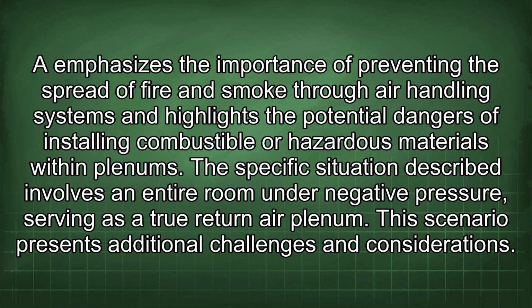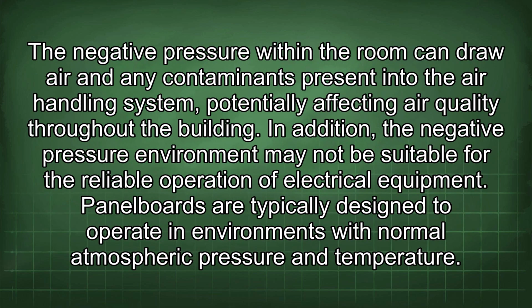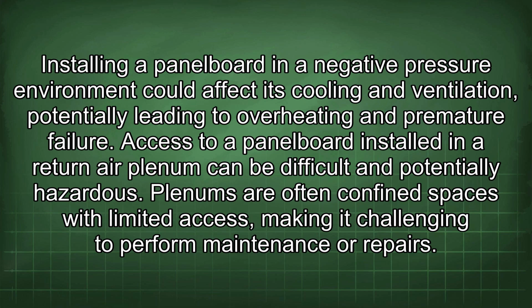The specific situation described involves an entire room under negative pressure, serving as a true return air plenum. This scenario presents additional challenges and considerations. The negative pressure within the room can draw air and any contaminants present into the air handling system, potentially affecting air quality throughout the building. In addition, the negative pressure environment may not be suitable for the reliable operation of electrical equipment. Panelboards are typically designed to operate in environments with normal atmospheric pressure and temperature. Installing a panelboard in a negative pressure environment could affect its cooling and ventilation, potentially leading to overheating and premature failure.